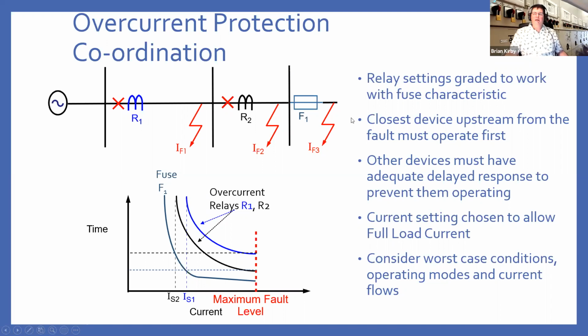So that if you get a fault here, as I said, your fuse will go first, whereas these other 2 will be time graded to operate only for the faults associated with their part of the network. So that is how you would perform coordination. Obviously, this is a small, simple case, but you may have multiple buses running in parallel, and you may have to grade across sections. So you may have to divide your network up into zones and grade each zone independently.